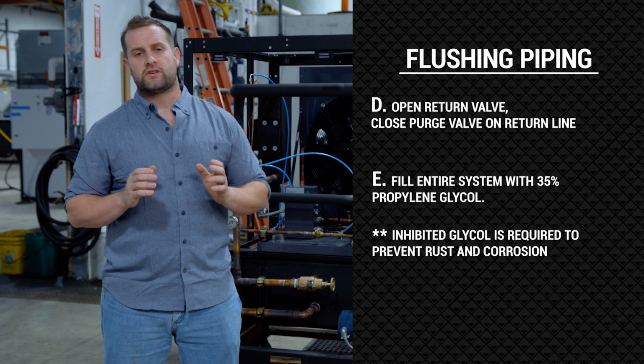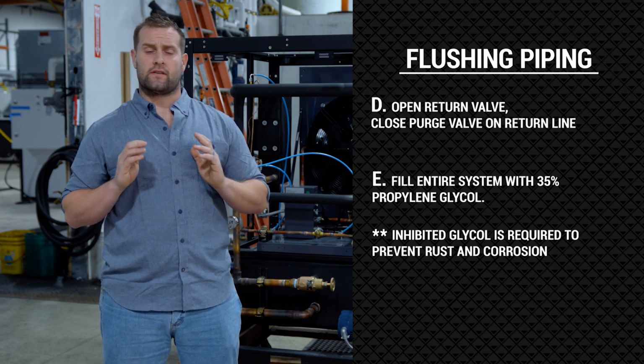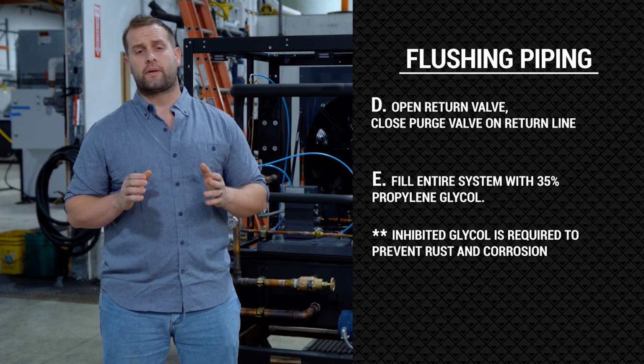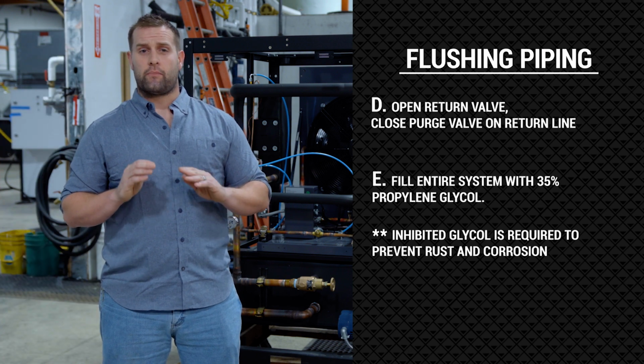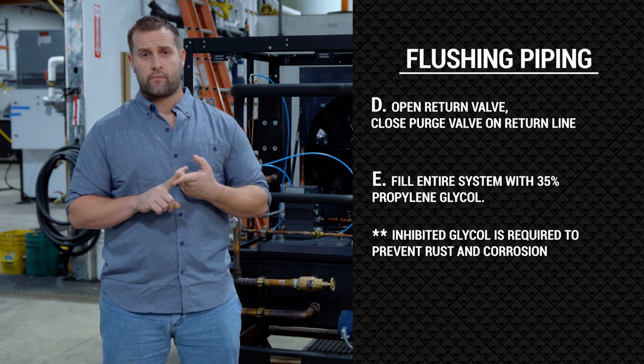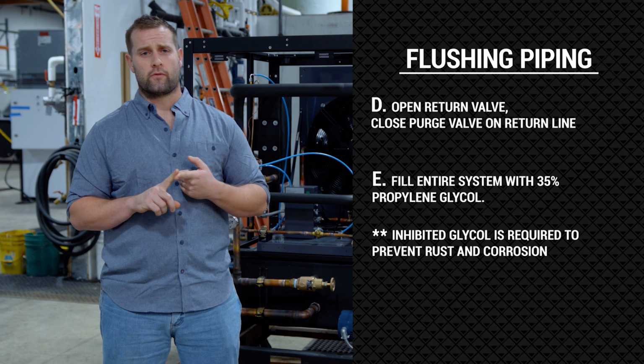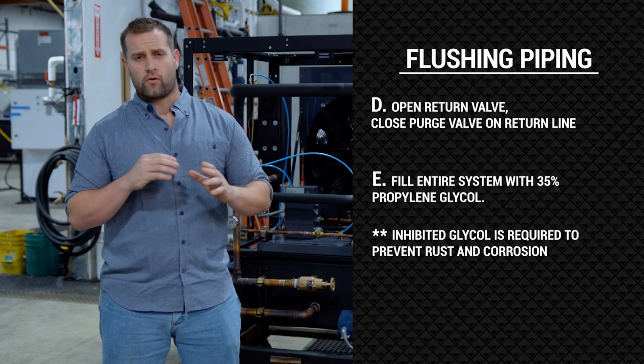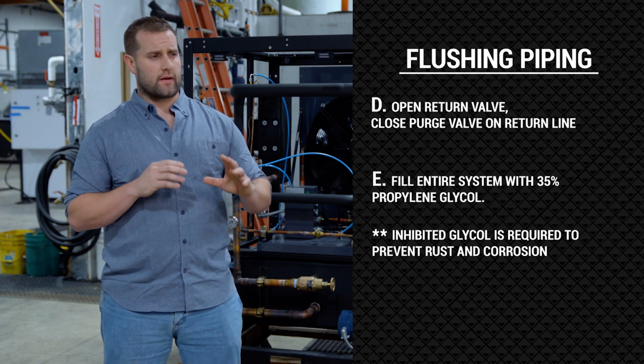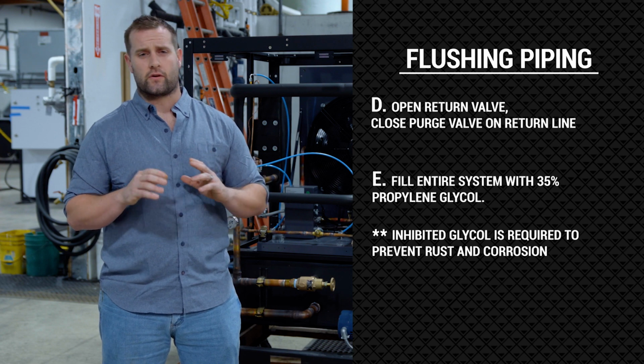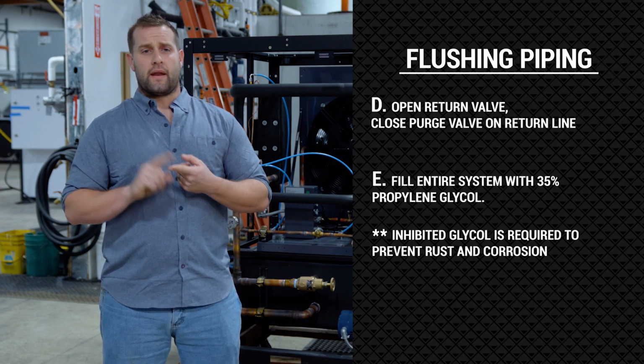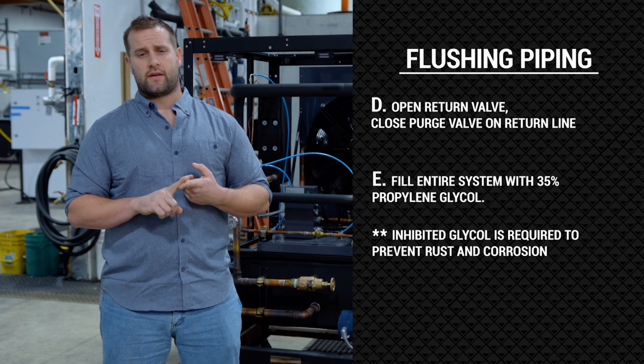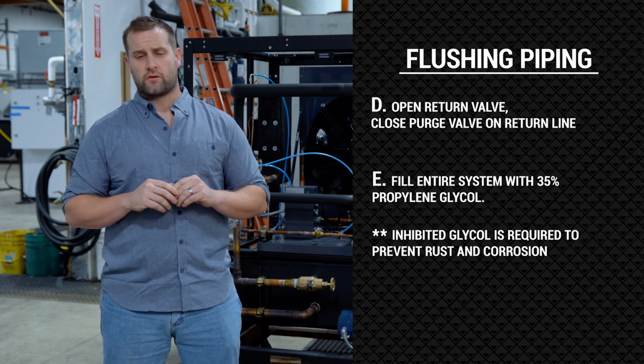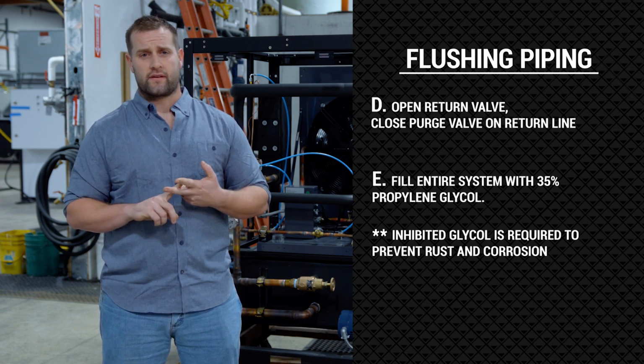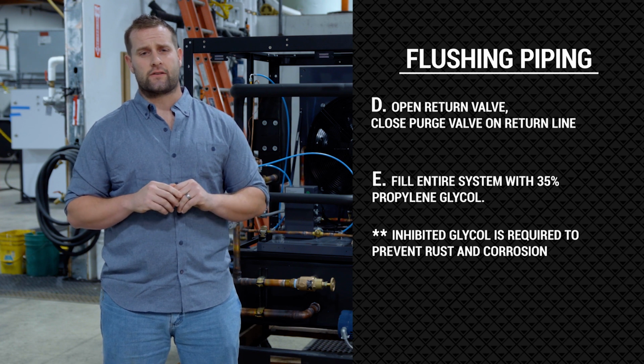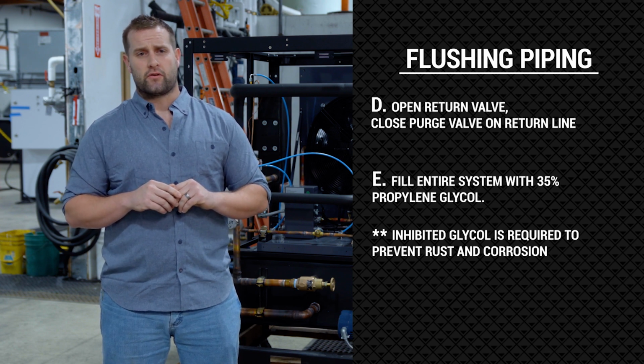Furthermore, after flushing your process piping, this is when you're going to want to add your propylene glycol. It's very important right off the bat that you have inhibited propylene glycol. Those inhibitors are important for organic growth, corrosion, stuff like that. You don't want your process pipe to affect your glycol at all. So inhibited propylene glycol is a must, and we're looking for a 35% mixture with your reservoir full, your process piping full, and all your jackets or any other equipment in your process.